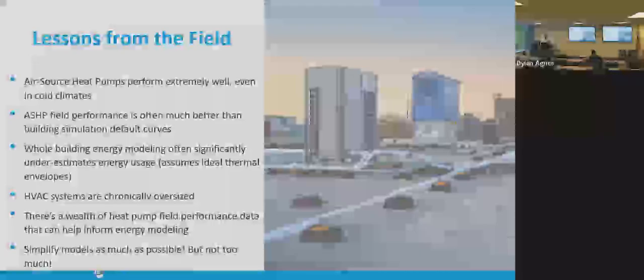Whole building energy models often significantly underestimate the energy use of real buildings. The DOE prototype models oftentimes have very idealized envelope models with very low infiltration, and those significantly underestimate the heating load. So many times when you just take the standard models, it's going to show an HVAC EUI of like 10 in a cold climate, and you're like, I've never seen an existing building have an HVAC EUI that low. And that's just what the standard is.